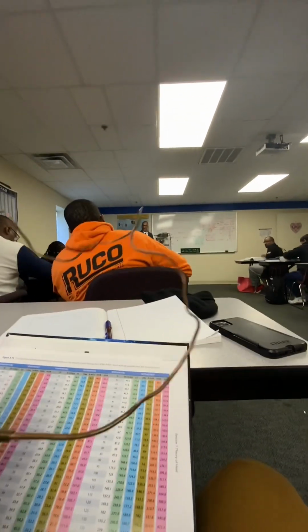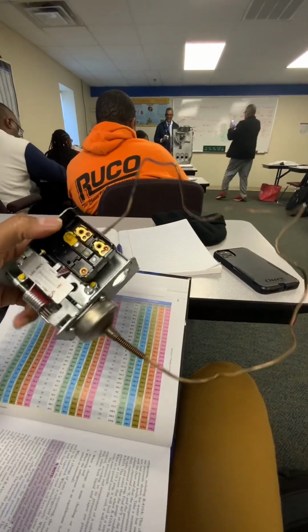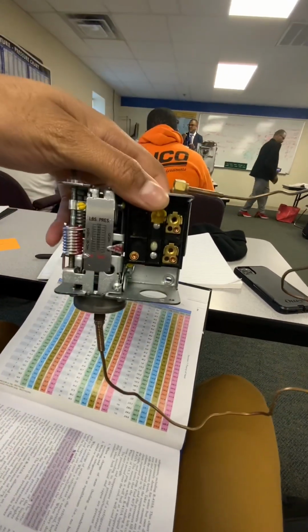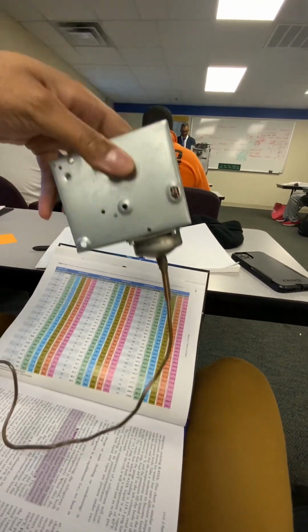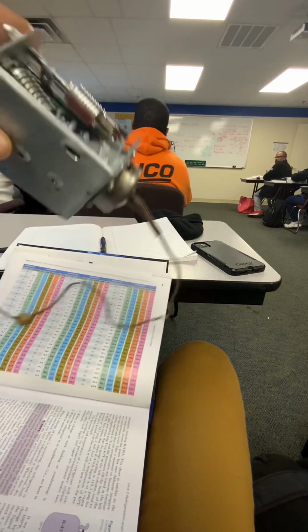Which is a fixed metering device. It has no moving parts per se. Then there is a capillary, referred to as a cap tube, which is also a fixed metering device, which means, again, we'll be going over this stuff so much. Don't get blown away. Pistons, actually, don't pump like a piston in a compressor. A piston is inserted in a line set that creates restriction.